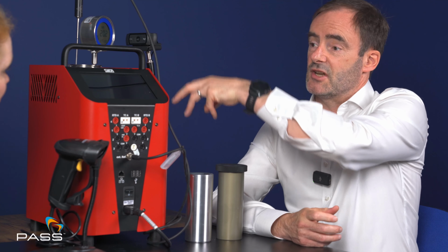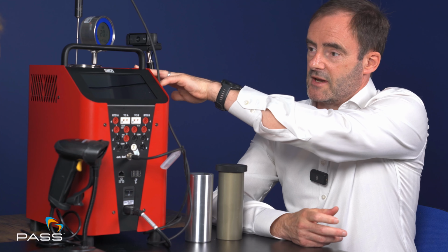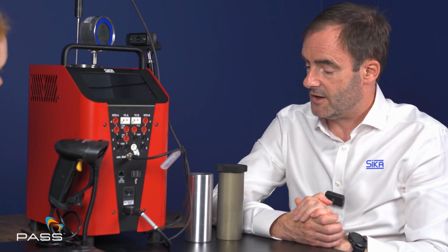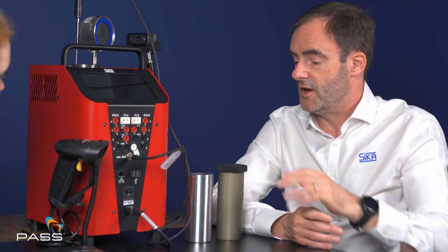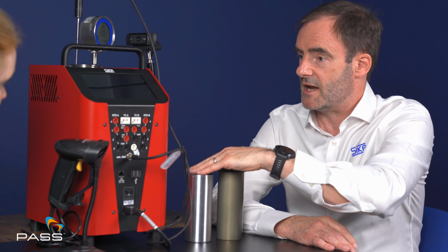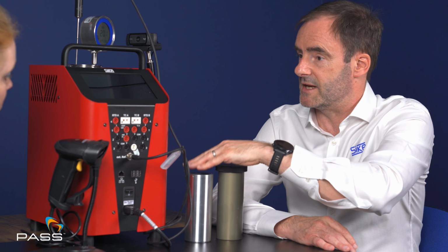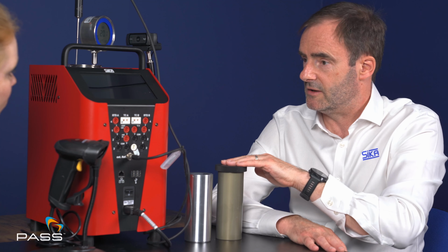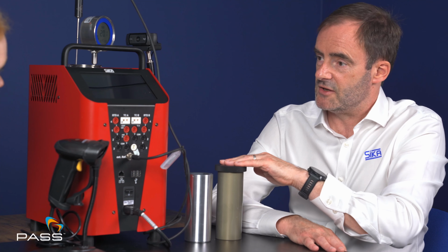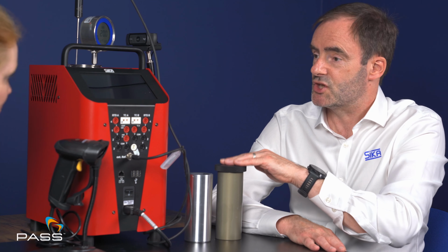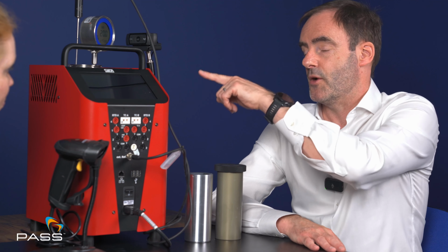What we can also do is slide that dry block out of the calibrator, and then we can put different versions in. In here we have the infrared calibrator for infrared guns. We can calibrate those. Yeah. And we also have a wet bath, which is silicon oil, and we can calibrate various sensors of different shapes and sizes, which won't necessarily go into a hole.